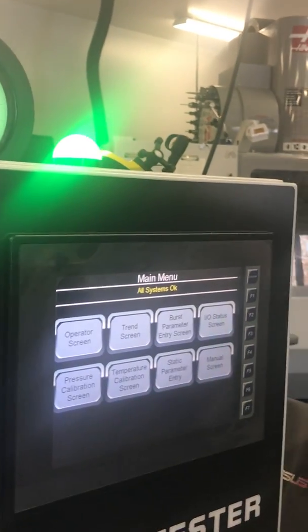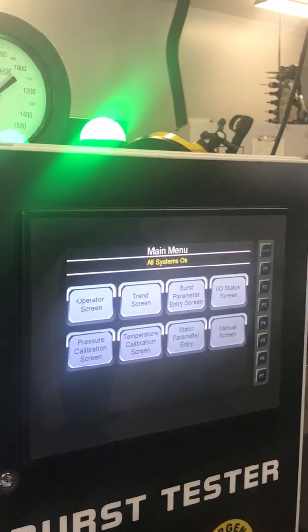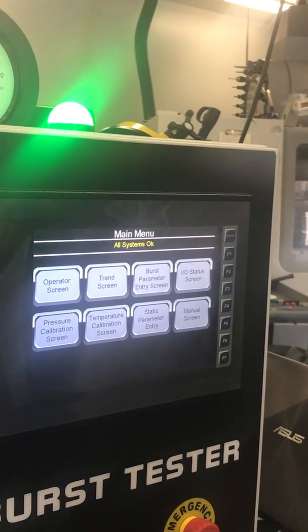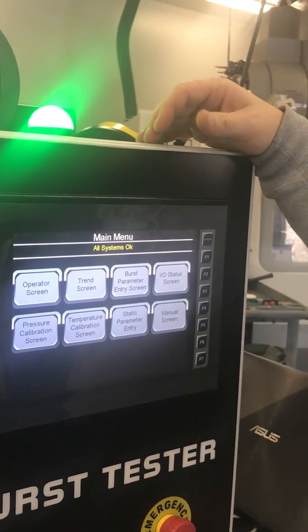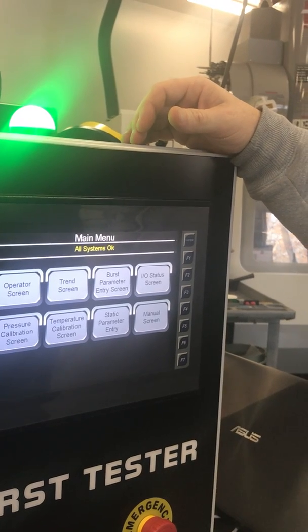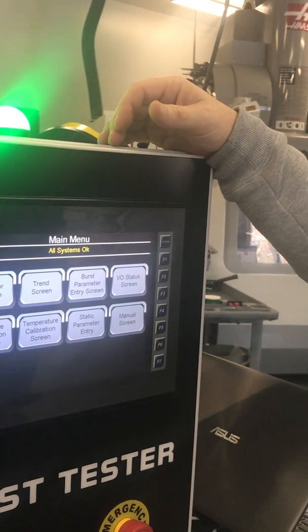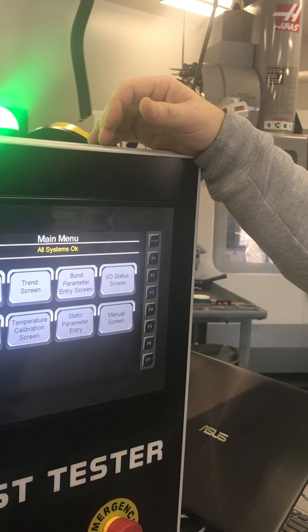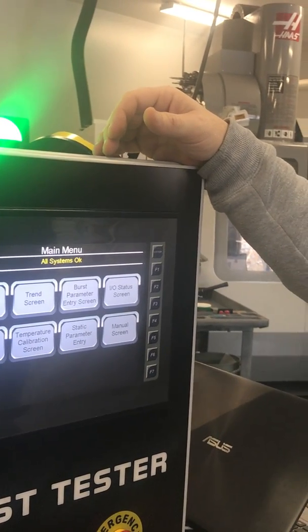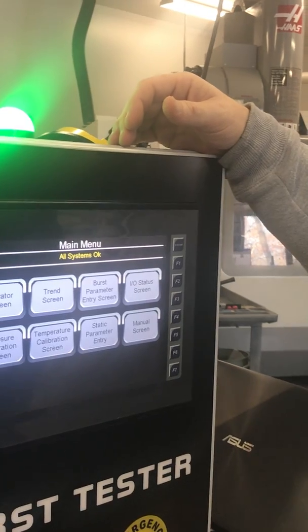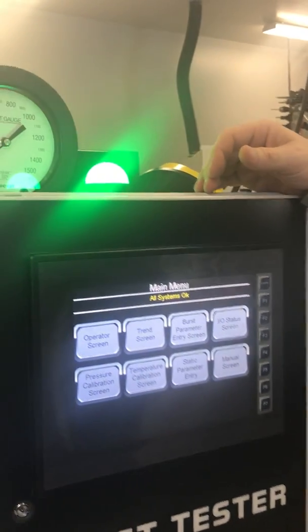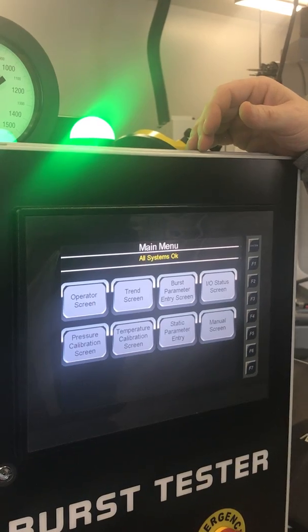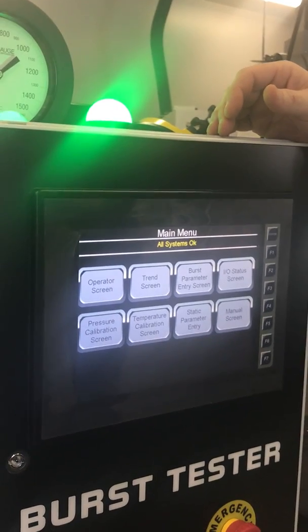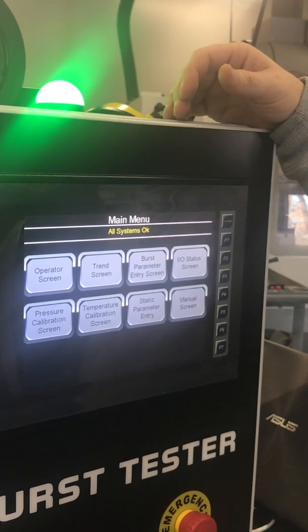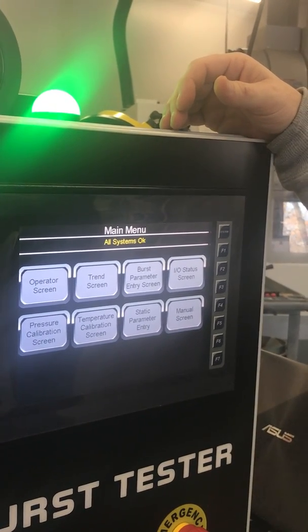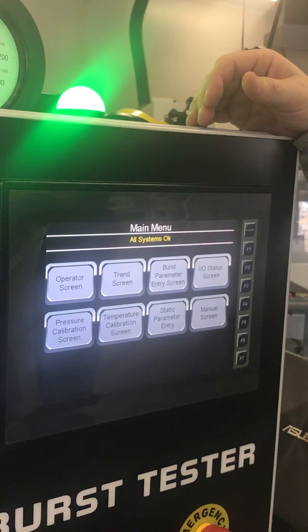Keep in mind this weird thing: if you've got well water that's cold at 52 degrees, and your room is at 85 degrees and your parts are at 85, and you run 52 degree water through them, you've just changed the game. The more you control all the temperatures and keep it that way, the more all your data will be the same. That's what we want to do. Even though it's air conditioned, that doesn't mean it's going to be 75. You need to keep this at 75 or less if you want to comply with an NSF test. It's probably going to be set at about 70.